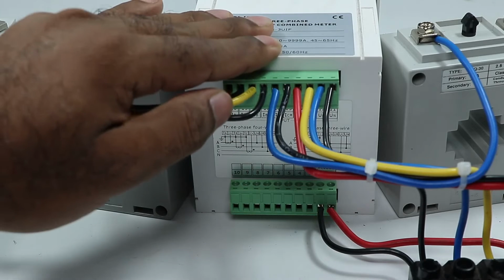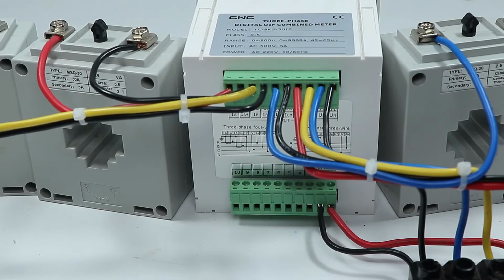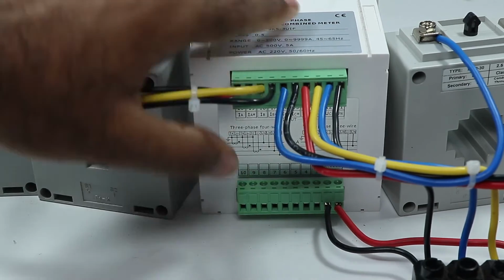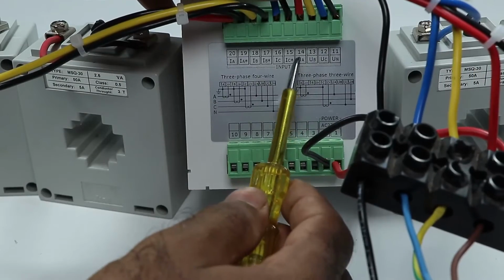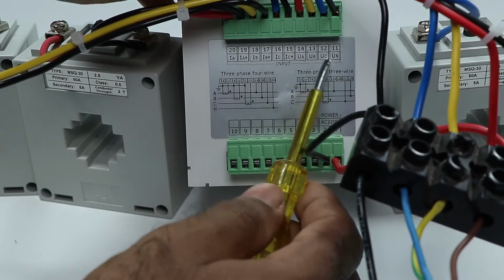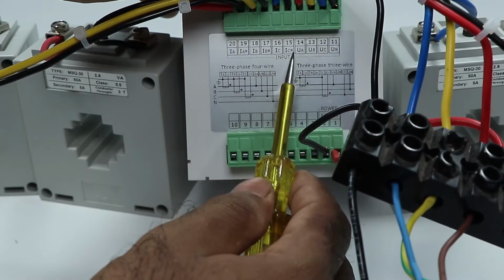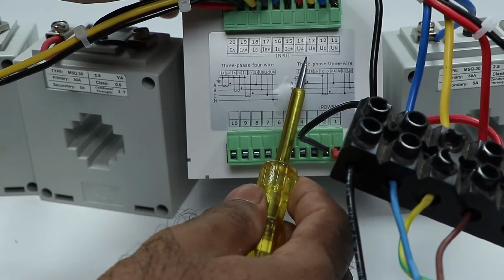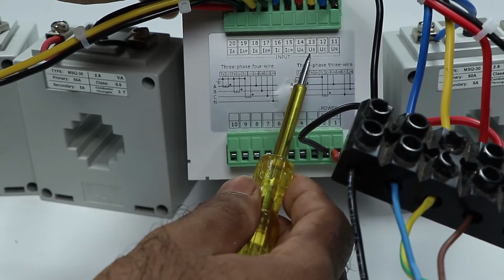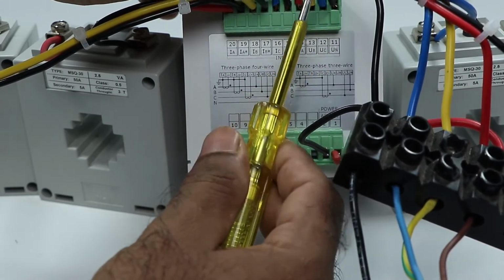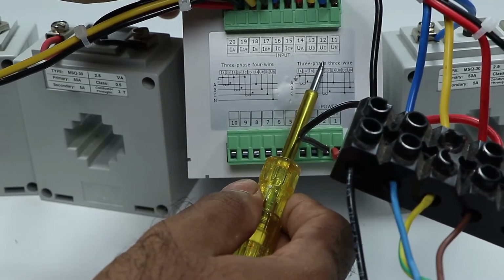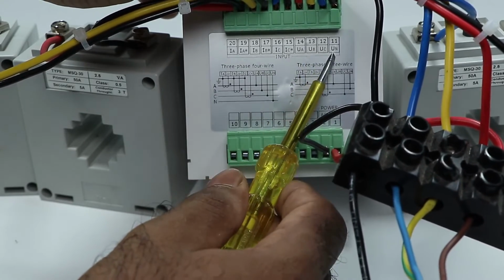Now through this meter I also want to measure the voltage, so we have to provide the feedback for voltage. For this, on the meter terminals UA, UB, UC, and UN are written. UA means connect R phase power supply at this point, UB means Y phase power supply connects here, and UC means B phase power supply connects here. At UN, you connect the neutral phase power supply.